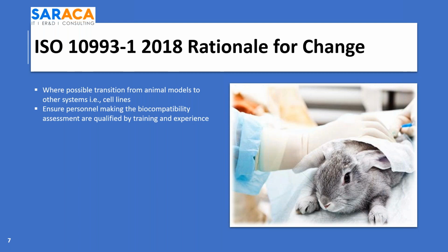This is a very important one, and you'll see it carried through the remainder of the standard as well. And that becomes a problem with a couple of the parts dealing with toxicology. I have to say there aren't that many toxicologists around to share between the notified bodies who are going to come in and look at your biocompatibility testing, or FDA, and assess whether your personnel are adequately trained to do the job, when there's not enough people to do both sides of it, notified bodies and the companies. I expect that would be rectified over time, but during a recent seminar I went to, it was a major fear that there weren't enough people to answer this change.